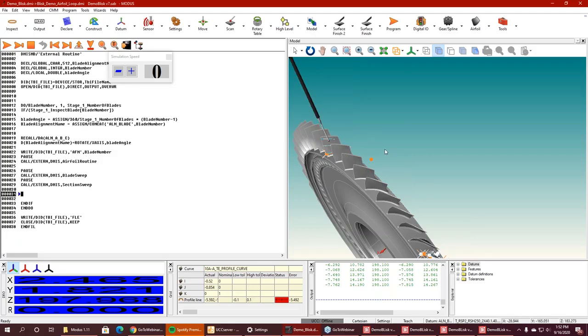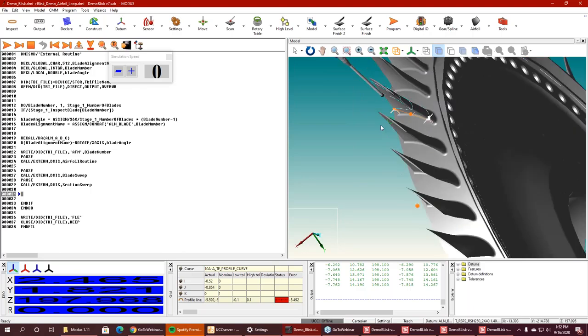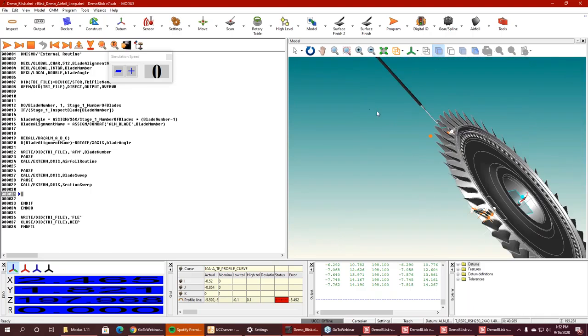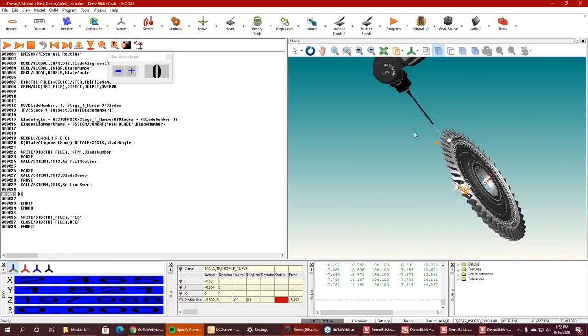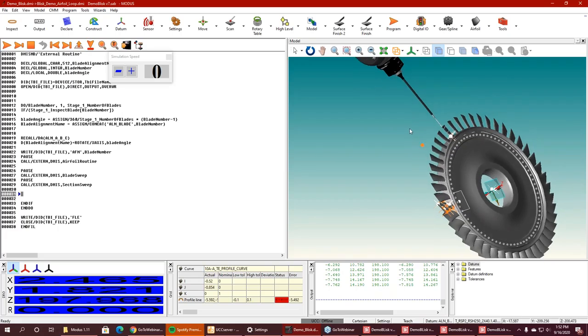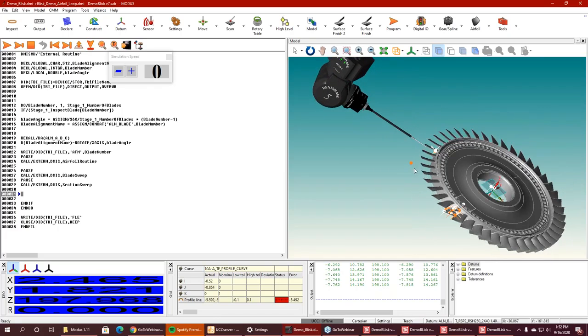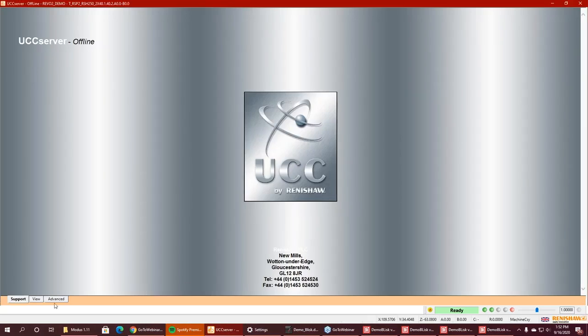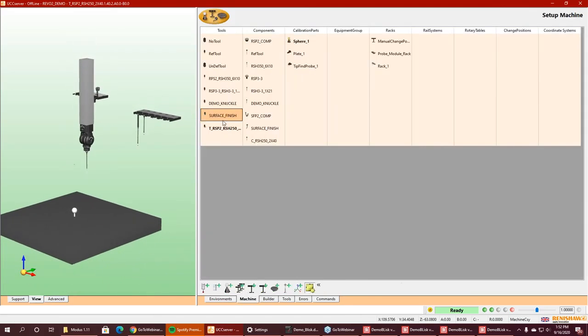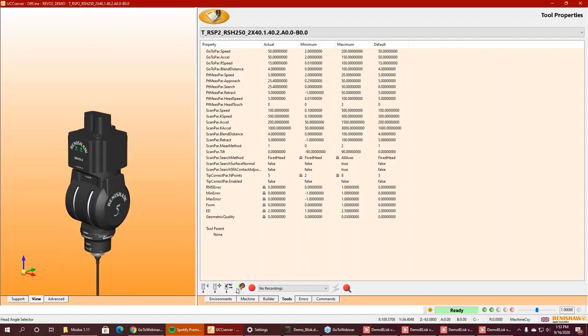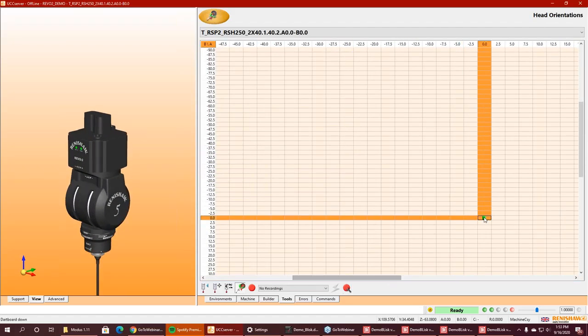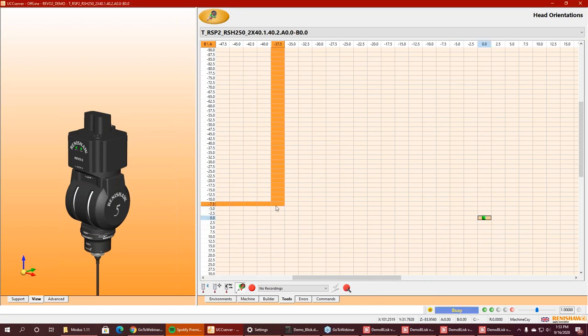That's great, Ben. And I touched on this a little bit, but speak a little bit more for me about the calibration, because obviously we're looking at this blisk, and you just said that all the angles and everything automatically align. But there's a lot of angles there with all those different blades. So does that mean that I have to sit there and calibrate for hours on end to make sure that every single one of those blades can be inspected, or how does that work? Oh no, the probe calibration is as simple as right-clicking on the tool in your UCC server. We have open right here. You go to your tools list and you find 00 in your list. Right-click and hit Requalify, and that calibrates every single angle. It takes about 20 minutes, 25 minutes, depending on if it's been calibrated before. But after that, every angle has been calibrated.